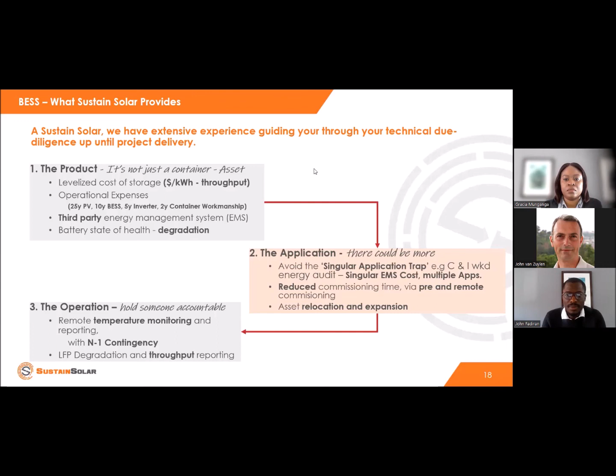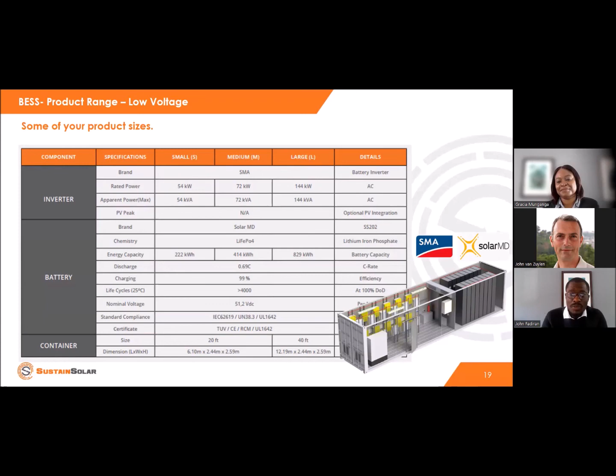What we have here is our low voltage product, designed in a 40-foot container. Pay attention to the ventilation and temperature control inflated in the container, along with fire suppression. This is built around SMA inverters and solar MD batteries, offering a very good cycle rate. We have options of 4,000 to 6,000 cycles, which is industry standard at 25 degrees Celsius. This is one of the solutions we've put into the market.